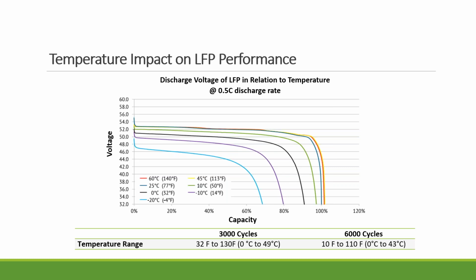Now, what's the impact on the battery's lifespan? There are mainly three factors, the first being the charging and discharging rate. Ideally, you want the battery to be charged and discharged at less than 0.5 C. Just to give you an example, for 200 amp hours, 1 C will be 200 and 0.5 C will be 100. So basically, you want to discharge the battery with 100 amps or less. That's good to prolong your lifespan.